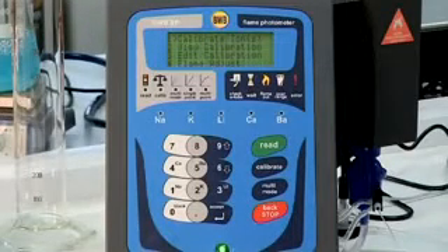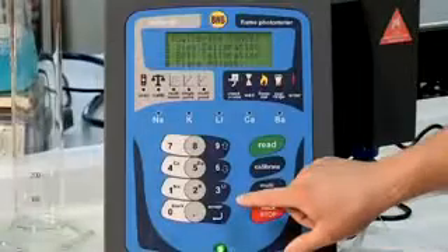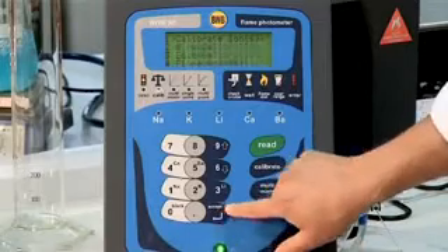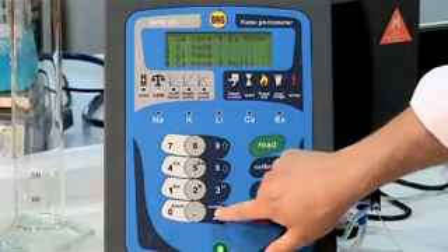The Bwb Xp offers the user a multiple ion multi-point calibration. For this calibration, 3 ions will be used: sodium, potassium and lithium at 3 different concentrations. Standard 1 has 90 parts per million sodium, 40 parts per million potassium and 10 parts per million lithium. Standard 2 has 100, 50 and 20 respectively. Standard 3 has 110, 60 and 30 also respectively.